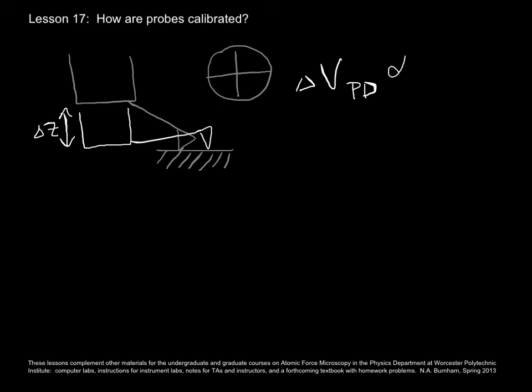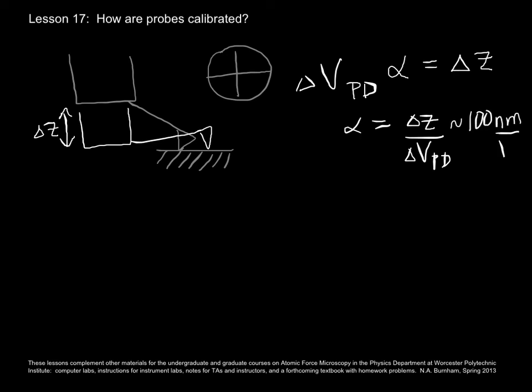We're looking for this calibration factor alpha, connecting it to the change in scanner height. So alpha is delta Z over delta VPD. Say that fast 5 times. It is typically about 100 nanometers per volt, but you must check that. You must check it every time you change a cantilever, or every time you change the position of the laser light on the cantilever.